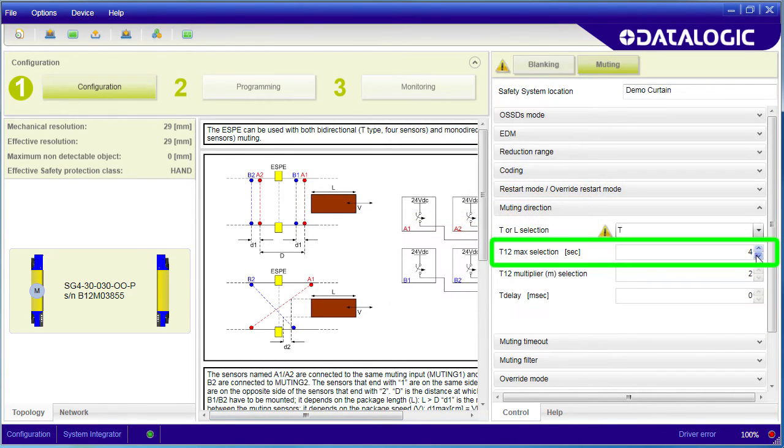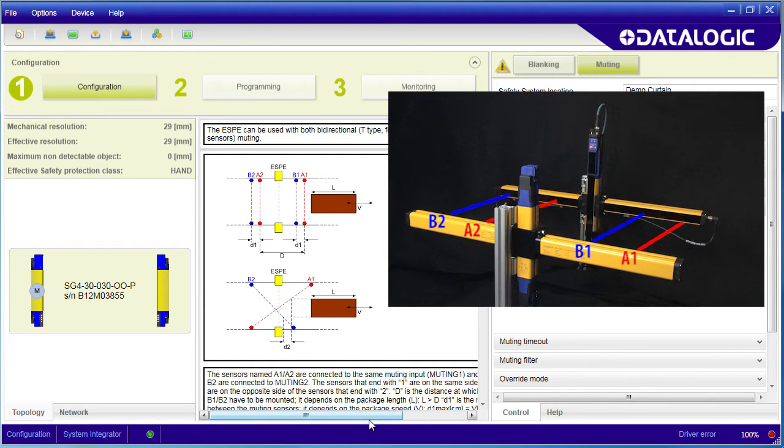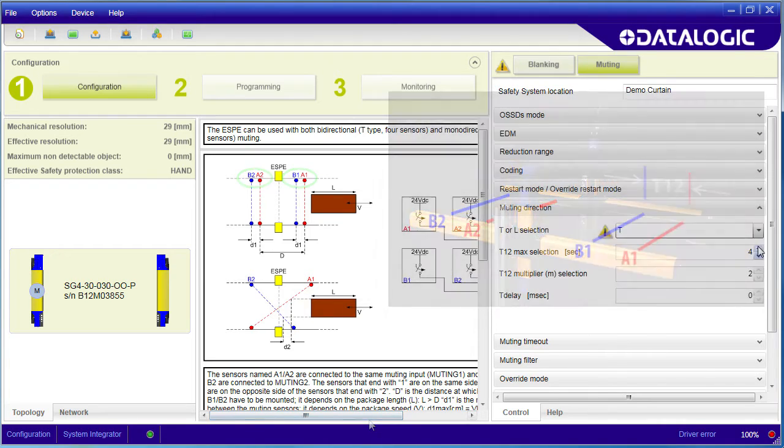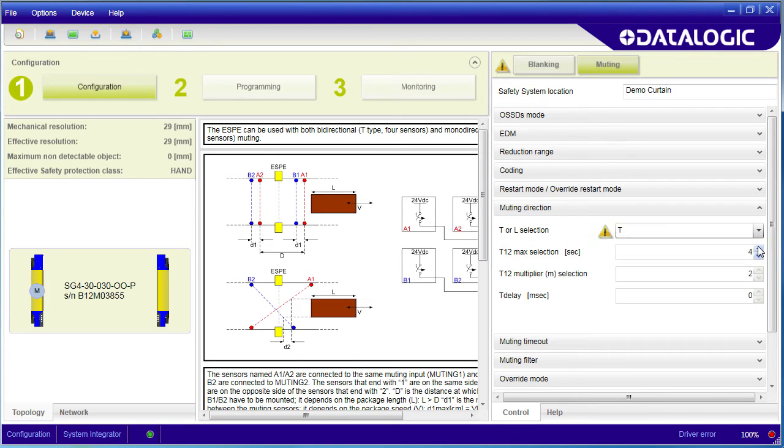This T12 is the time it takes the package to go from the A sensor to the B sensor, which is how fast the package is moving. You are specifying the max time here which indicates the slowest velocity which will invoke the muting. Since we have two sets of sensors in this T configuration, we know when the package is finished passing through the light curtain.